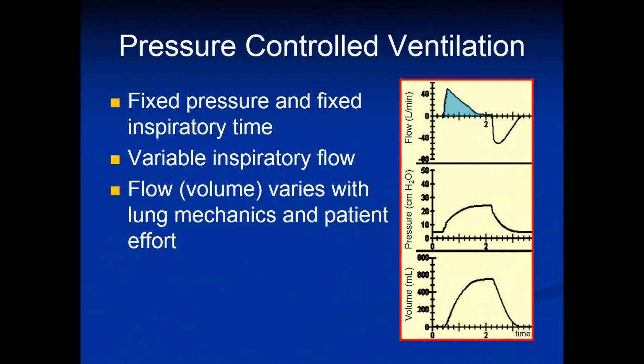In pressure-controlled ventilation, we deliver a fixed pressure and a fixed inspiratory time. The inspiratory flow rate is variable, meaning that flow and also volume varies based on the lung mechanics and the patient's effort. Many believe that having a flow rate that can be basically controlled by the patient may actually be beneficial in terms of patient comfort, although there is not any strong evidence out there that supports this comment.